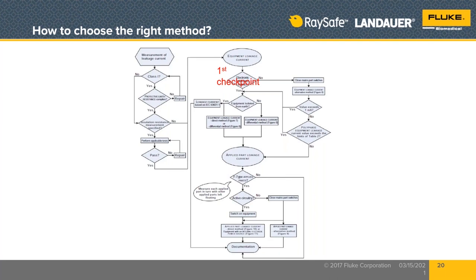From there, we get to our first checkpoint, which is, does the device under test have a power switch? There are medical devices that do not have a power switch. They are turned on as soon as you plug it into mains power. That would be an example of a medical device that does not have a power switch. If it does not have a power switch, then we will move where it says no power switch, and we'll come down this decision tree. But we'll get there in a minute. If the device that we're testing does indeed have a power switch, then the answer is yes, and we'll proceed straight down on the decision.